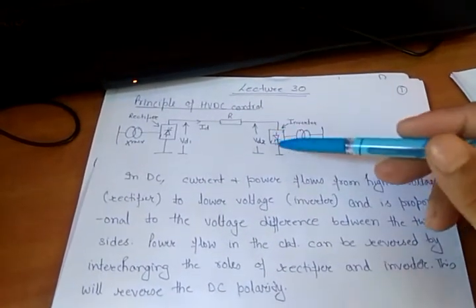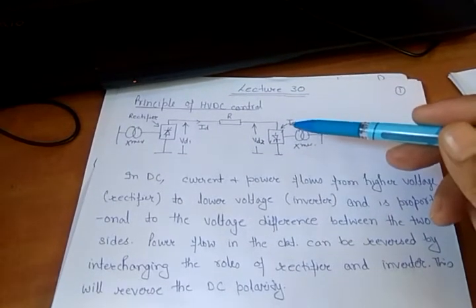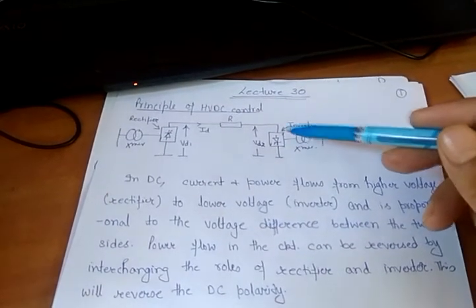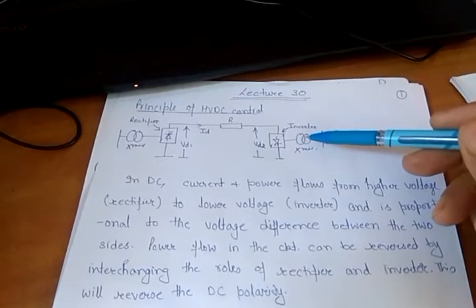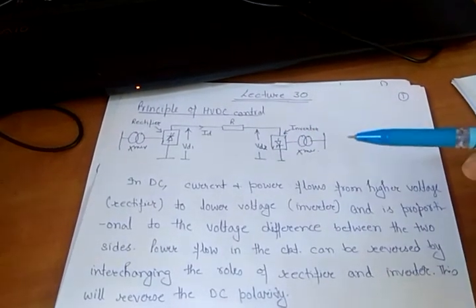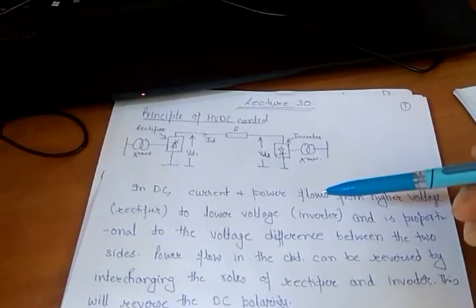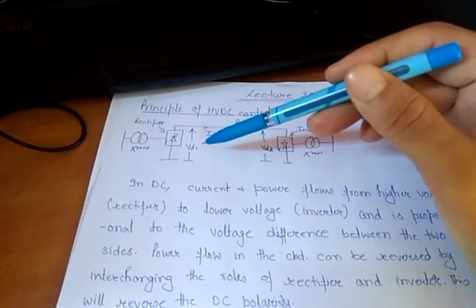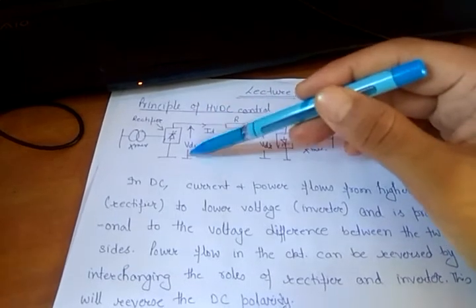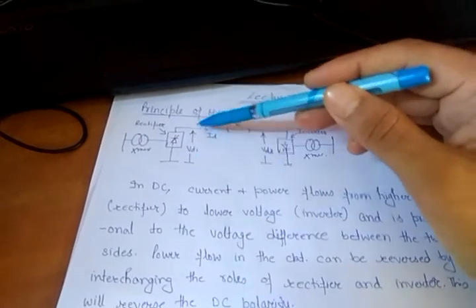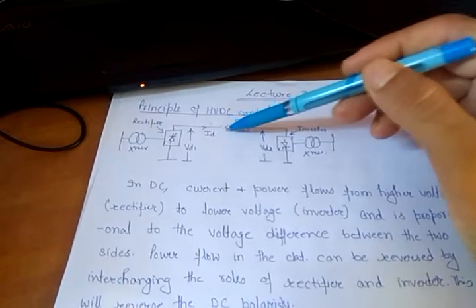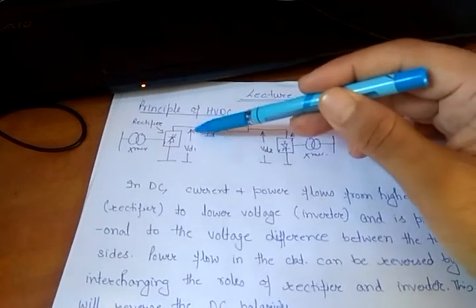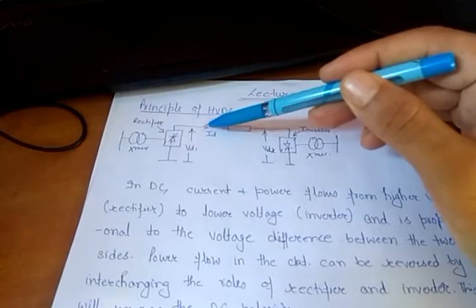In HVDC, generally the inverter station is controlled such that the direct voltage of the system is fixed, and it has a relationship with the voltage on the AC side. The other station, called the rectifier station, has its direct voltage adjusted so that the current flowing in the system is controlled to the desired transmitted power.